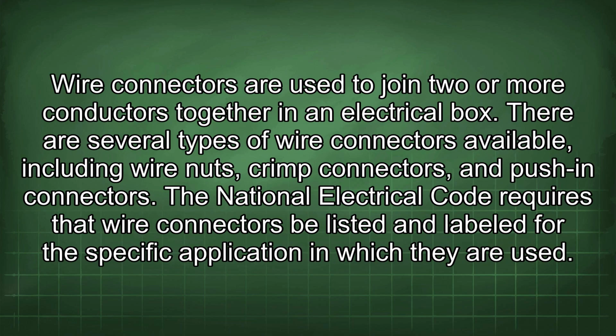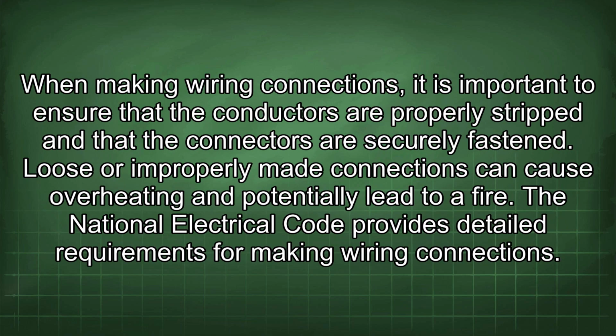Wire connectors are used to join two or more conductors together in an electrical box. There are several types of wire connectors available, including wire nuts, crimp connectors, and push-in connectors. The National Electrical Code requires that wire connectors be listed and labeled for the specific application in which they are used. When making wiring connections, it is important to ensure that the conductors are properly stripped and that the connectors are securely fastened. Loose or improperly made connections can cause overheating and potentially lead to a fire. The National Electrical Code provides detailed requirements for making wiring connections.